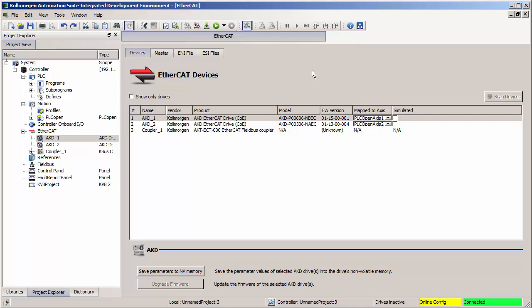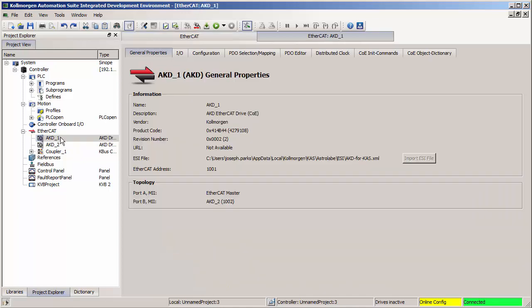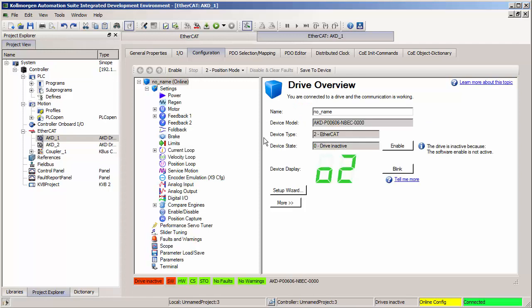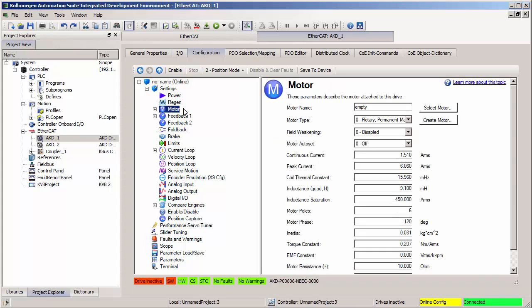Once the online config mode has started, you can choose an AKD drive under the EtherCAT section of the project explorer. When you double click, it shows up in the main window. And when you click on the configuration tab, it will load all the drive commissioning or setup screens. It's very nice to be able to do this without a project running, so you can go into the motor tab to make sure that the right motor and motor parameters are all selected.